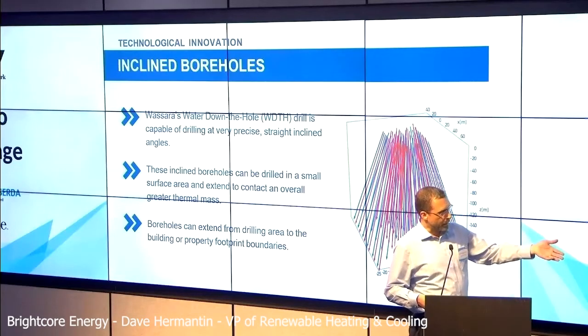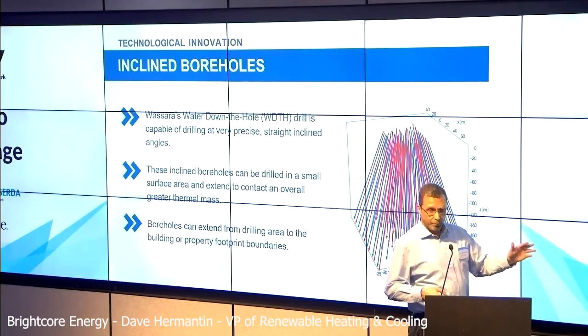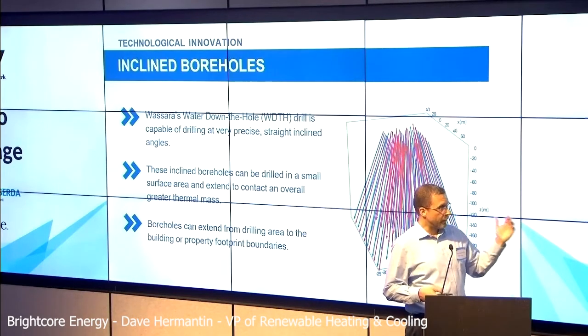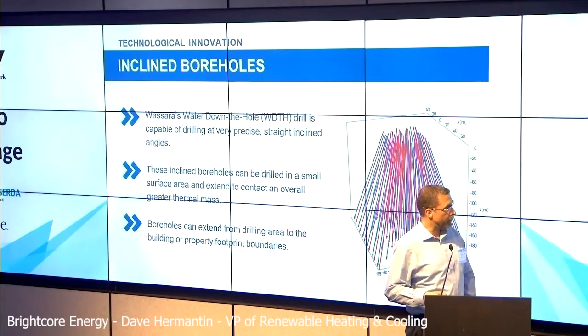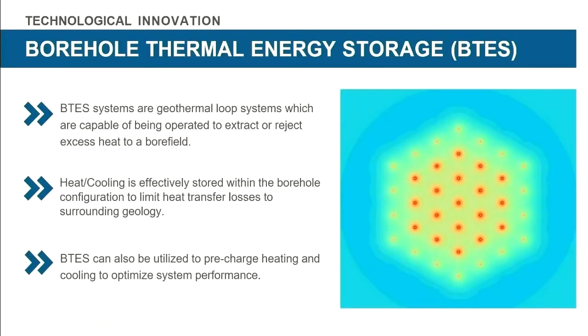So they went down from grade down to about 650 feet, and they stayed on the property. The drilling is very accurate, and we can survey it. It's generally as accurate as 1% to 2% from deviating from where our terminating points are designed to be. But today we're talking about thermal energy storage. Another inherent quality of ground source systems is their ability to provide thermal inertia, or kind of act as a capacitor that can buffer the loads of a building. And in a sense, this does qualify as thermal energy storage if you're using these systems to offset upcoming loads.